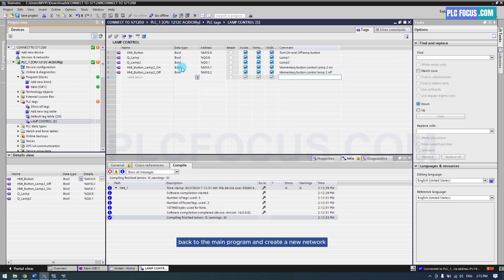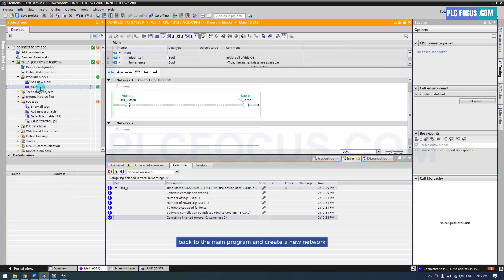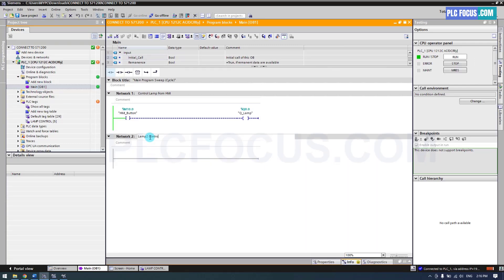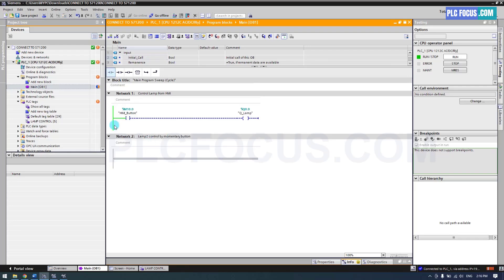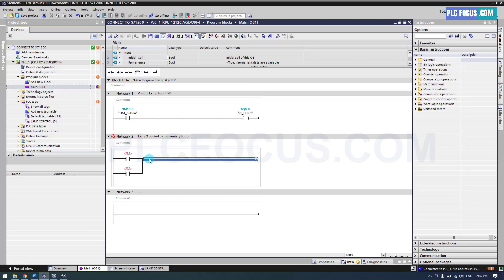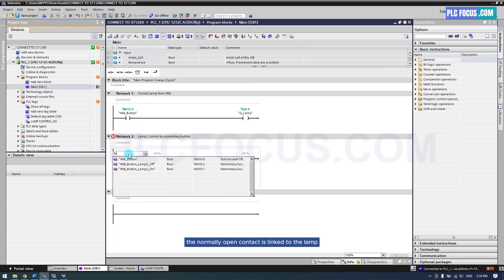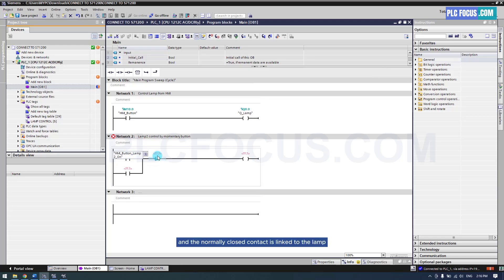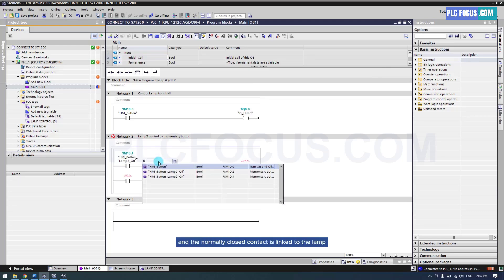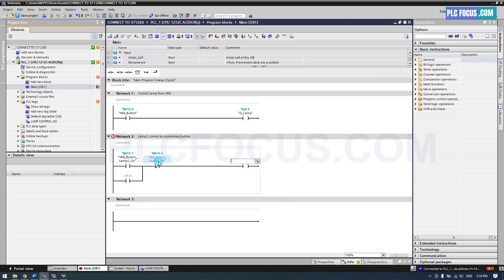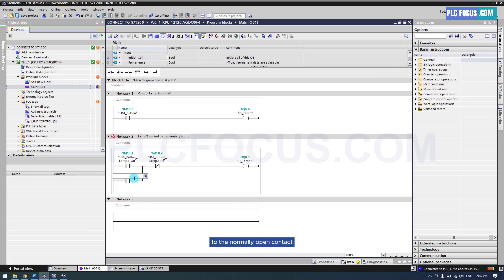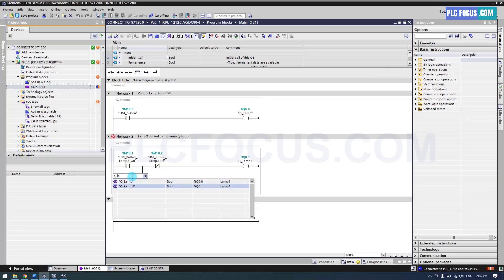Back to the main program and create a new network for the momentary button. The normally open contact is linked to the lamp on button tag, and the normally closed contact is linked to the lamp off button tag. The output is Q0.1. We also need to maintain the circuit when the on button is released by linking the lamp tag to the normally open contact in parallel with the on button.